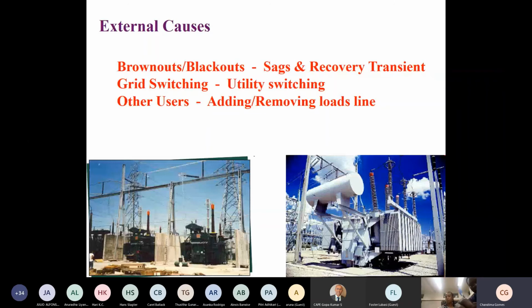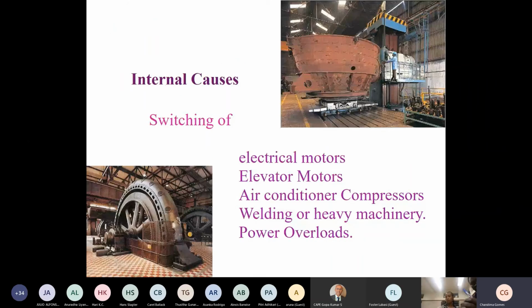And not only from external means, even the internal environment can generate transients. Whenever you are switching electrical motors, air cons, any inductive load, you can get transients. And also something that I have not mentioned here, and during the last couple of years, I have done a lot of research in that area. Whenever you are switching on and off, actually energizing and de-energizing, if I say in the very correct terms, because it happens automatically, the power factor correction capacitor banks, especially if you have centralized power factor correction capacitor banks, their energizing and de-energizing processes can create some sort of transients of ringing nature, which can be harmful to your equipment.